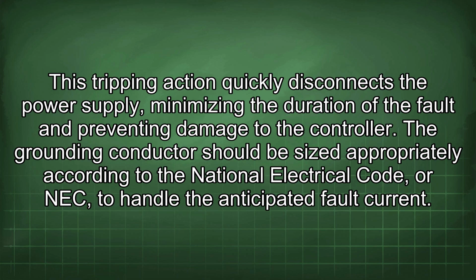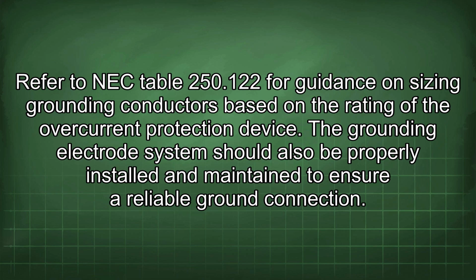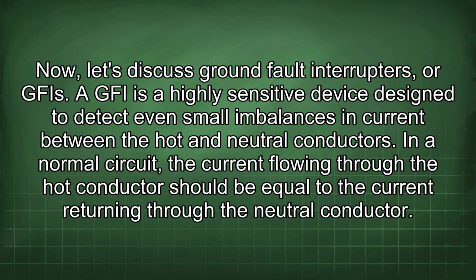The grounding conductor should be sized appropriately according to the National Electrical Code, or NEC, to handle the anticipated fault current. Refer to NEC Table 250.122 for guidance on sizing grounding conductors based on the rating of the overcurrent protection device. The grounding electrode system should also be properly installed and maintained to ensure a reliable ground connection. Now let's discuss ground fault interrupters, or GFIs.